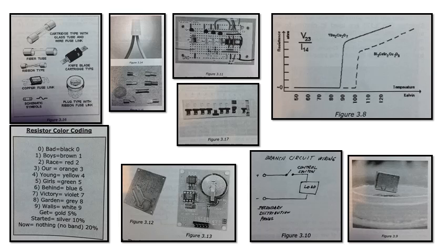The National Electrical Code sets a maximum voltage drop across each branch. A branch circuit, figure 3.10, is wiring from the panel to the last device on that circuit. A maximum of 3% voltage drop is allowed, and a formula can be found on page 59 of your text. This formula can be very helpful when trying to figure out a conductor size that will not cause a high voltage drop.